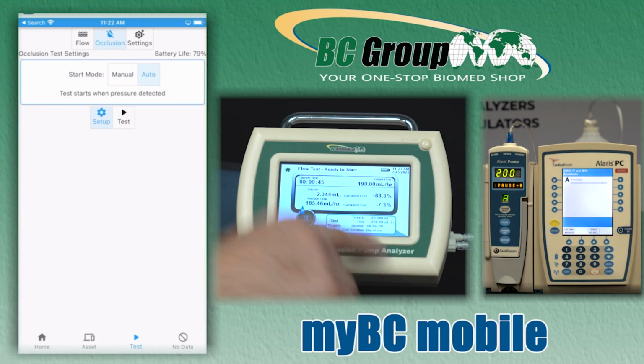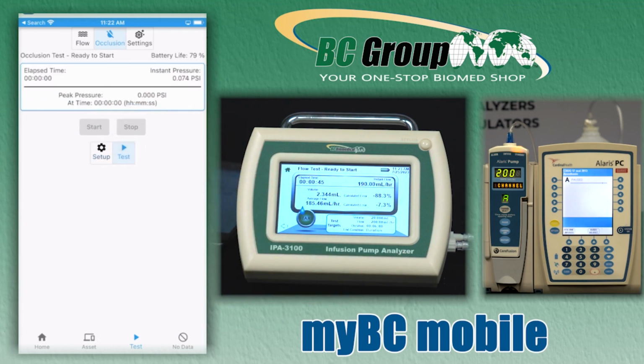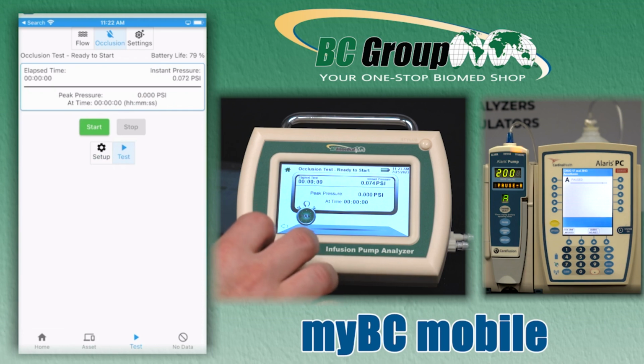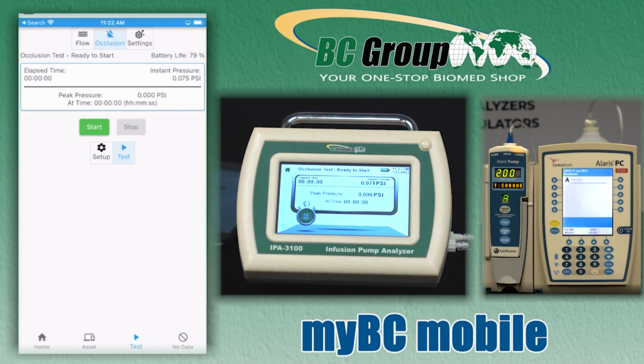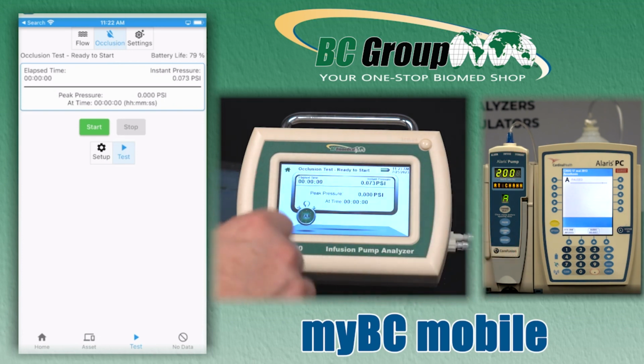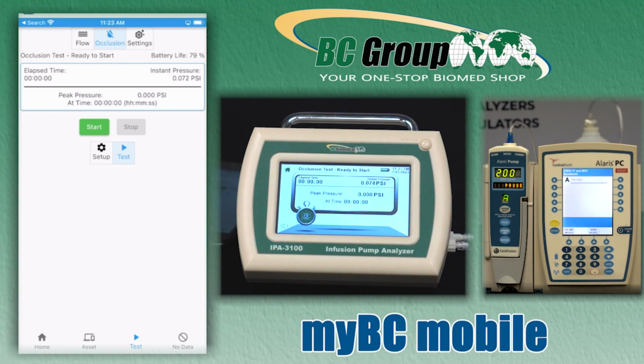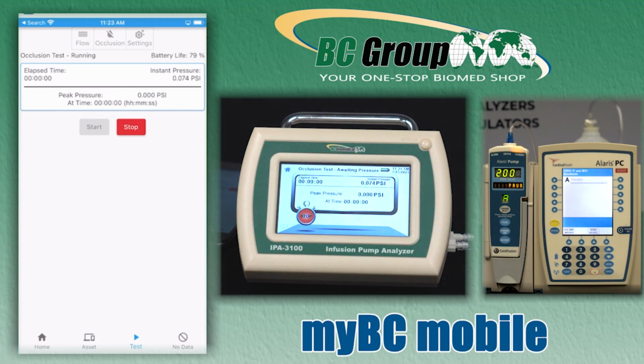This is at the screen that was doing the flow test. And so we'll see when I start this test, it automatically updated the screen. It configured the settings. It's showing me the current pressure measurement that's live. And we can see that the elapsed time hasn't started yet. So when I start the pump, it's going to start this timer and then we'll get our occlusion test. So I'm going to press start on the BC Mobile. That started the test. We can see the 3100 is waiting for pressure. So if I restart the pump, it's going to trigger that test.